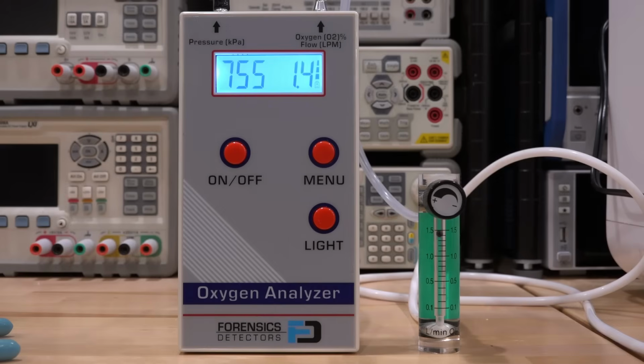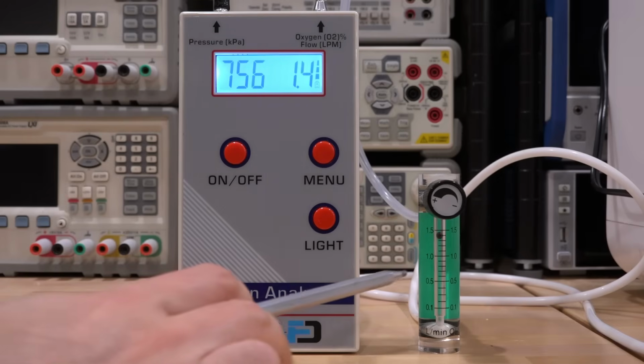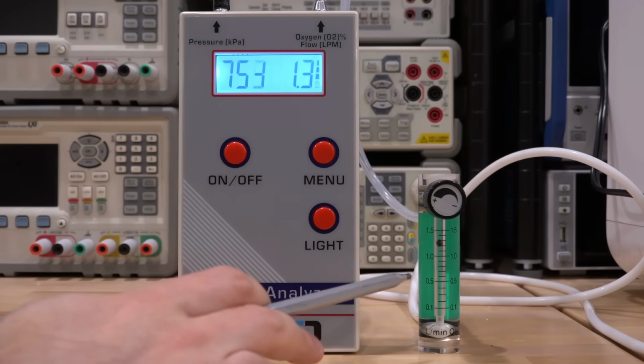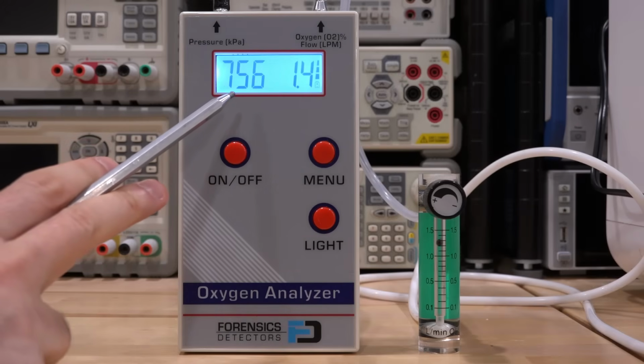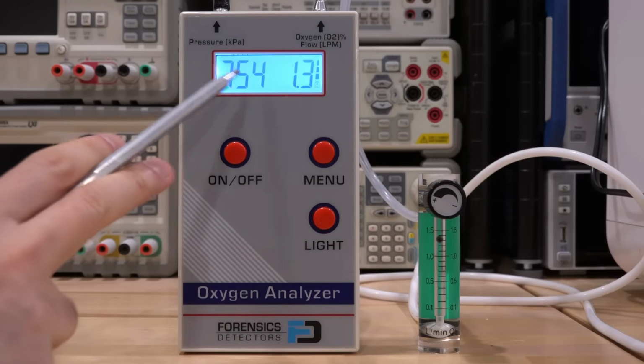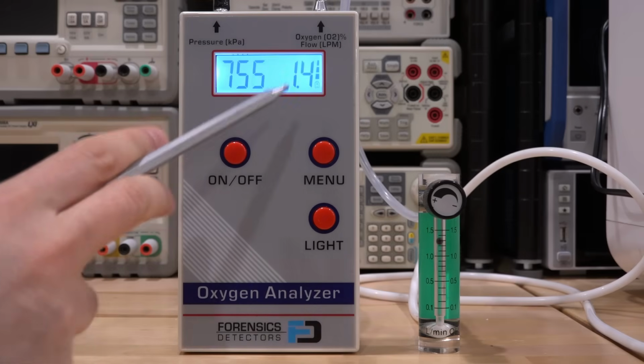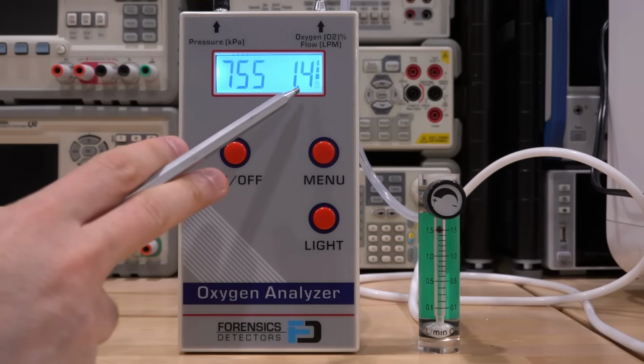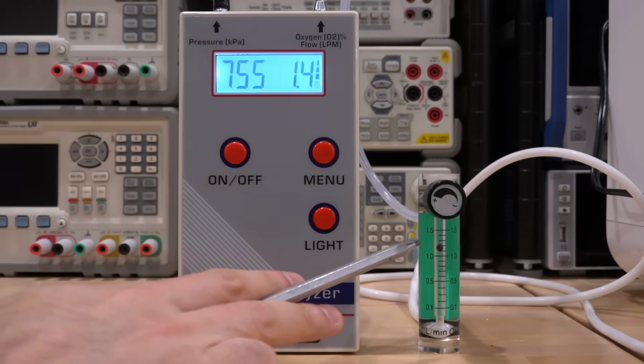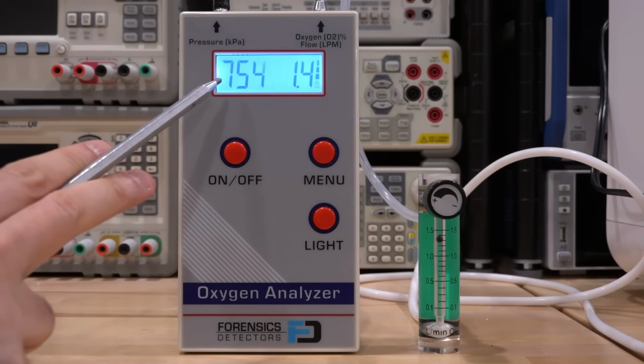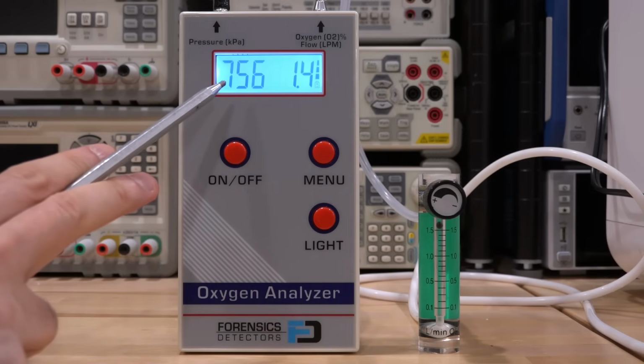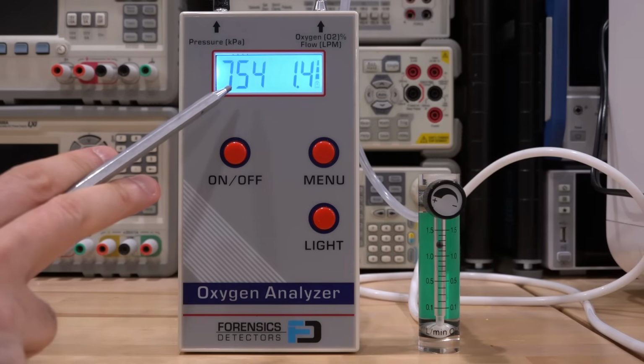Okay, so the system's been running for a few minutes and I've allowed it to stabilize. I'm passing the output of it through this flow meter here, which also allows me to adjust the flow if I want to. Right now it's wide open. The unit is set to 1 liter per minute. Here on the left side is the oxygen concentration. It's missing a decimal point. That's because this is a very simple LCD screen. And on the right side, we have the flow in liters per minute. This number and this number on average agree, so that's pretty good. This means that this is not even remotely close to 90%. So just like I thought, that number in the front is of course completely fake.